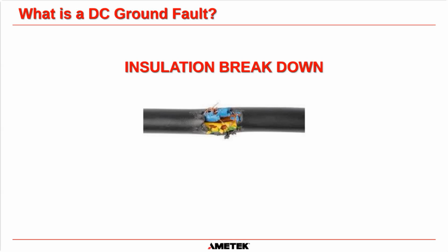And I love this picture because looking at it straight away, I've been in America for 10 years, but I can tell straight away that this is a UK cable. Blue is neutral, brown at the back there is hot, and this yellow and green one is earth ground. I don't know why that makes me smile, but it does. But that's a good example of insulation breakdown. Something has rubbed or nicked or broken that insulation down through into the cable conductor. Okay.